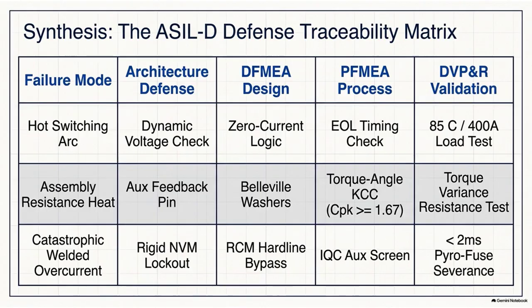What about the manufacturing assembly deviations? We keep coming back to those loose bolts on the bus bars causing impedance. How do you test for a manufacturing failure in a computer lab? This is perhaps the most impressive closure of the engineering loop, connecting the initial design, the manufacturing floor, and the final validation. In the physical testing lab, engineers go to a replica battery assembly station. They intentionally, maliciously misassemble the battery packs. Wait, they build them wrong on purpose?